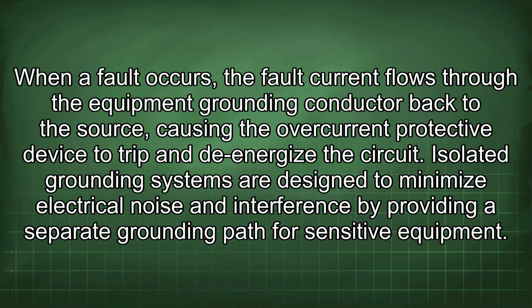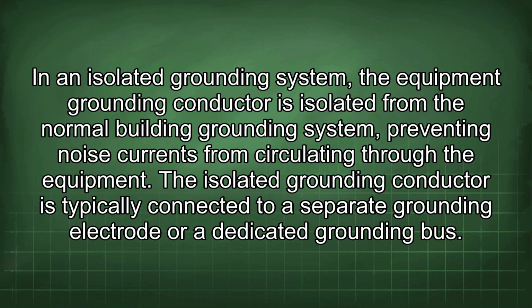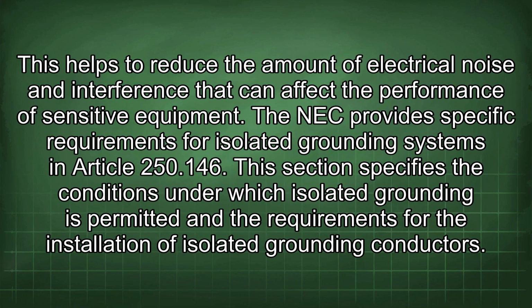Isolated grounding systems are designed to minimize electrical noise and interference by providing a separate grounding path for sensitive equipment. In an isolated grounding system, the equipment grounding conductor is isolated from the normal building grounding system, preventing noise currents from circulating through the equipment. The isolated grounding conductor is typically connected to a separate grounding electrode or a dedicated grounding bus. This helps to reduce the amount of electrical noise and interference that can affect the performance of sensitive equipment.